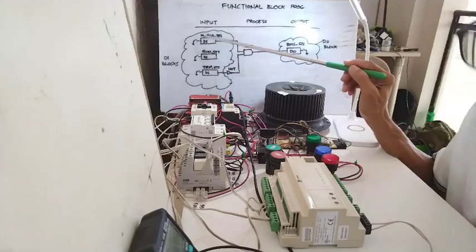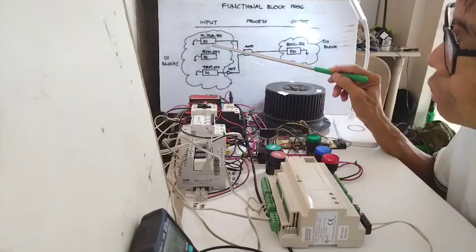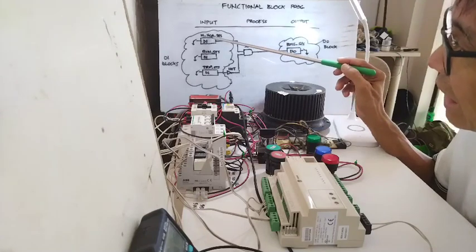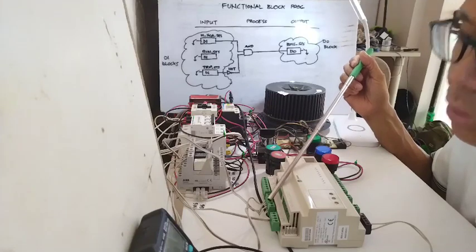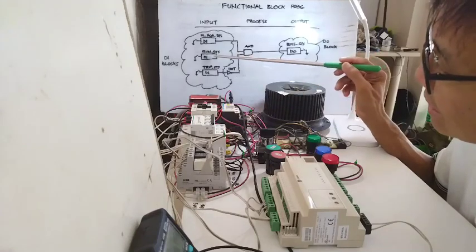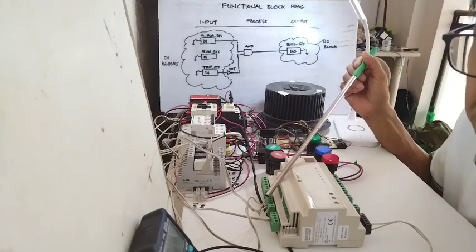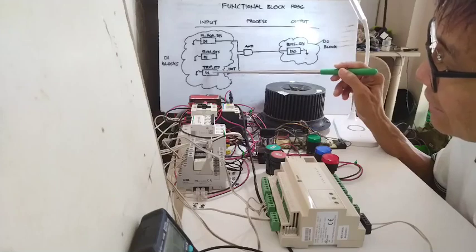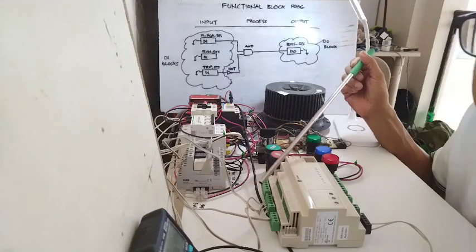These DI blocks need to be mapped — in building management system we call it mapping. When you say map, you need to map these points to the channel of your DDC. This DI one will be mapped to our first binary input. Then that binary input one will be cabled to the relay in your control panel. DI run status will be mapped to controller channel 2, BI 2. This third block, DI trip status, will be mapped to our controller's binary input number 3.